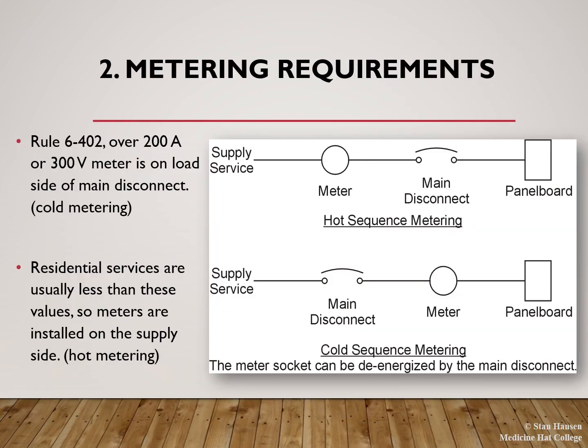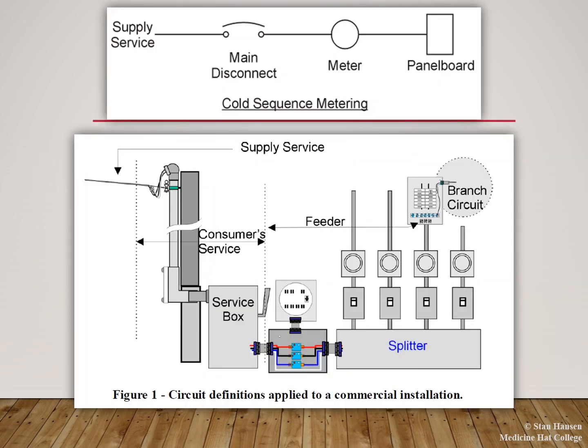Now that we've gone through our terminology, let's look at some of the metering requirements that we have depending on the type of service we're going to build. Rule 6-402 puts out the conditions of what kind of metering system that we can have. And we have a choice between cold sequence metering and hot sequence metering. Cold sequence metering is something that is typically used on commercial services.